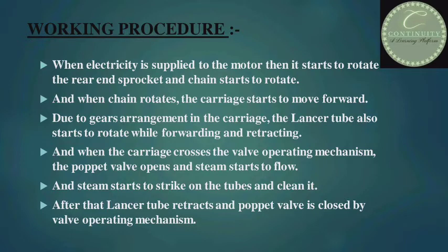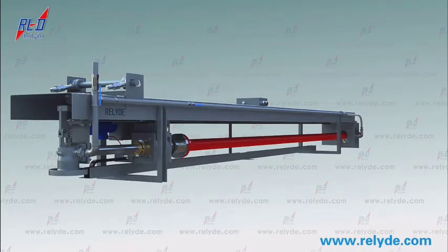Working principle of the soot blower: when electricity is supplied to the motor, it starts to rotate the rear end sprocket and the chain starts to rotate. When the chain rotates, the carriage starts to move forward. Due to the gear arrangement in the carriage, the lancer tube also starts to rotate while forwarding and retracting. When the carriage crosses the valve operating mechanism, the poppet valve opens and steam starts to flow through the nozzles, strikes on the tubes and cleans them. After cleaning, the lancer tube retracts and the poppet valve is closed by the valve operating mechanism. Now I am going to show you a video of the working of the long retractable soot blower — you can understand better from this video.